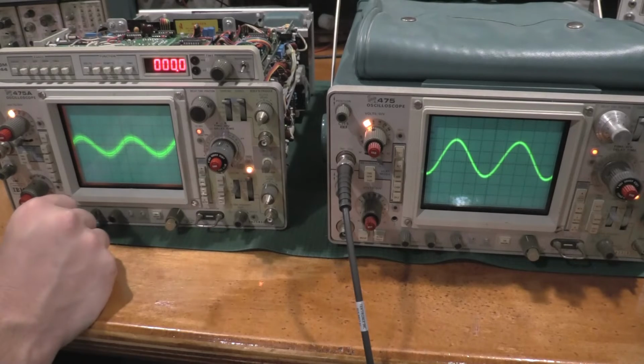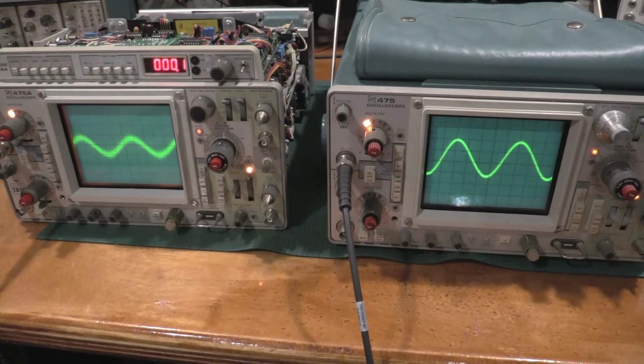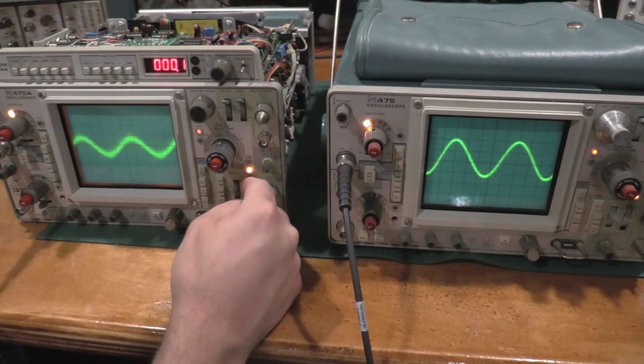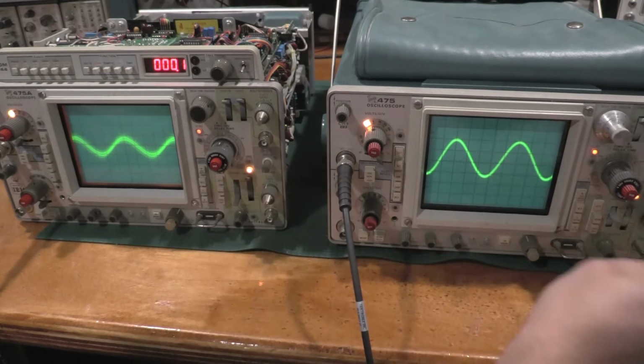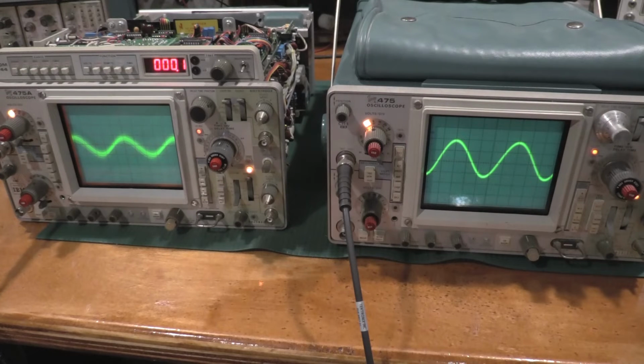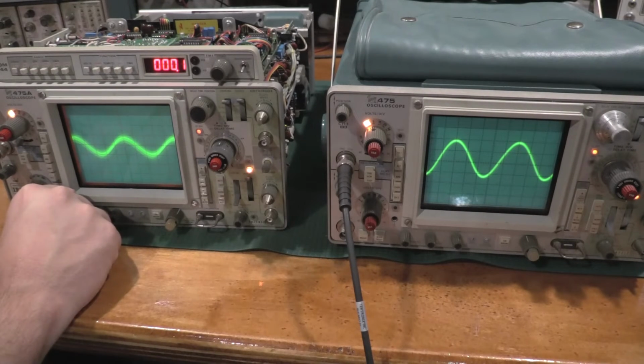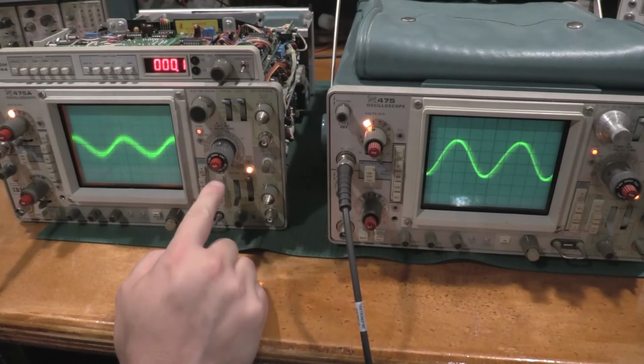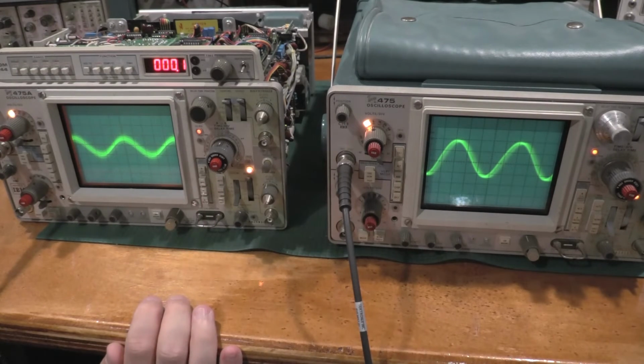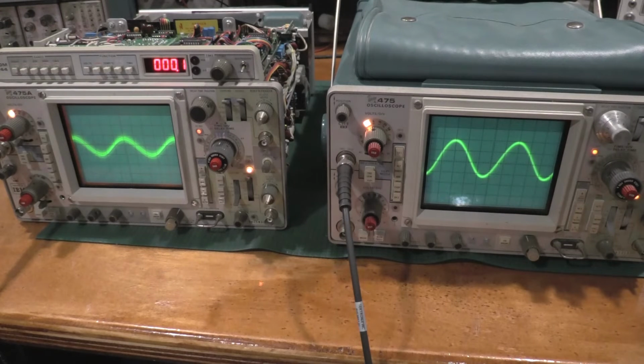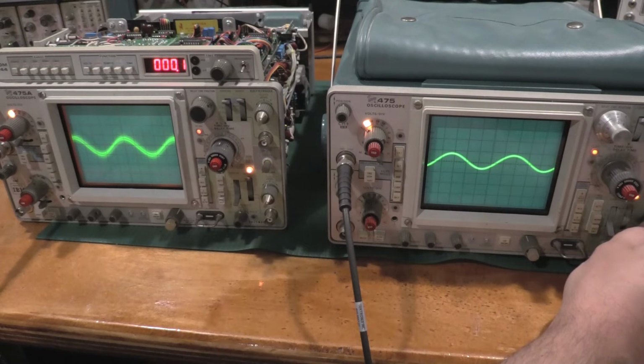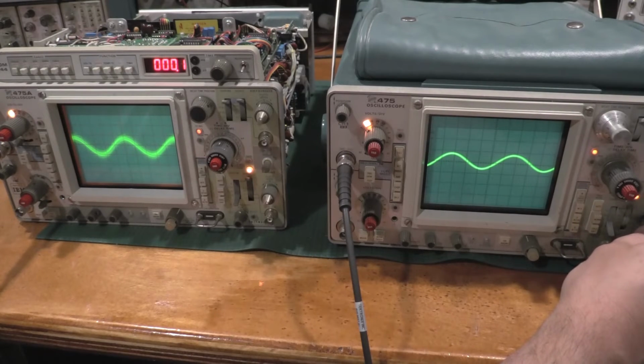Just different things Tek did during the time. So we're looking at trigger performance. I have the trigger set to low frequency rejection, but we'll switch them down to DC, so everything is fair, because we're going to really turn some speeds up. 10x magnifiers on. They are set at 0.01, so we are actually at 0.001, 1 nanosecond per division on each scope. And I'm going to make this fair. We're going to cut some amplitude down, because we have a very low amplitude signal. But we do have the ability to lock in.